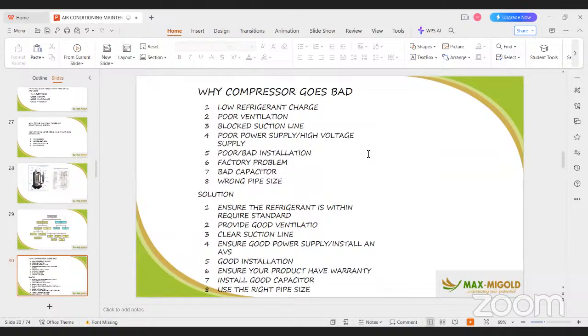Blocked suction line. Your suction line, your copper pipe, can actually be blocked. If you are installing that, dirt finally gets into your pipes, and it can actually block them. And if they block, there's no movement of the refrigerant. You know, all the four things I mentioned, the compressor, the condenser, the expansion valve, and the rest, are all connected together with a copper pipe. Some of them are 1/4, some are 1/2 inch, some are 3/4, some are 5/8, and the rest of them. If care is not taken, that blockage will not allow the flow of refrigerant. And if the refrigerant does not get to the evaporator, it will not deliver the cooling that you require.